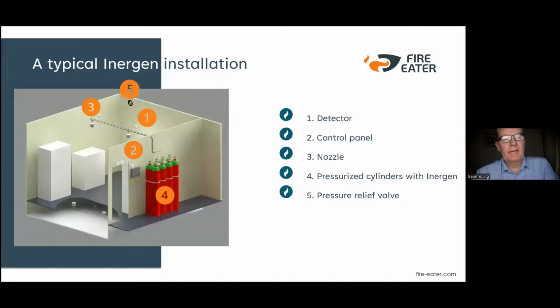So as you can see here, again, just to run through, it says it's a typical Inergen system, but to be honest, it's exactly the same for any type of gas, be it chemical or Argonite or Inergen or anything like that. So you have your risk, your room. You've got smoke detectors in the room and smoke detectors under the floor void. You also have your pipe network that goes into the room and under the floor void. You need to protect every zone or void within a given space.